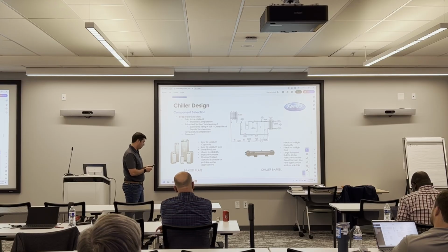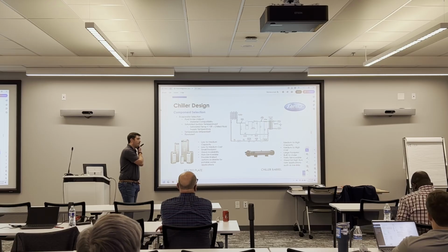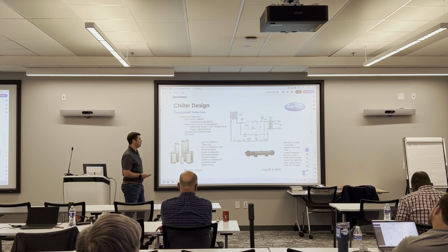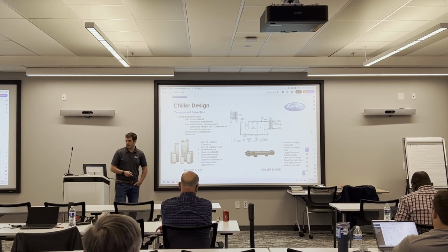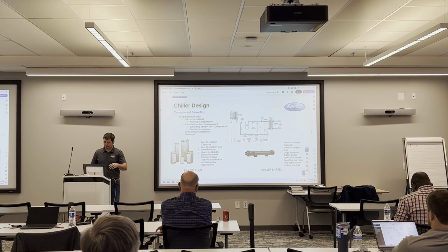And then the other option on the right-hand side here would be a chiller barrel. So these are good for medium to high capacity. It's a medium to high cost. Large footprint. It's a pretty long chiller barrel generally. They're generally built to order, fairly serviceable. Like you can change out gaskets, tubes if you have a failed tube. And they're great for high flow rate applications. So you'll see a lot of these in ice rinks. Ice rinks have a massive flow rate, very small temperature differential.